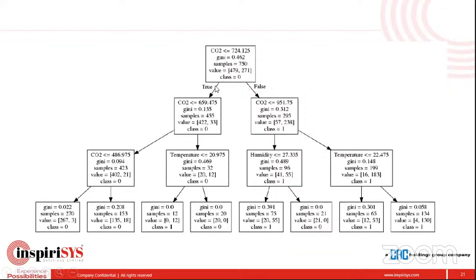So it will check first whether the CO2 value is less than 724. If yes, it will check again for CO2, and again for CO2 and temperature. Finally, class 0 means non-occupied, class 1 means occupied.